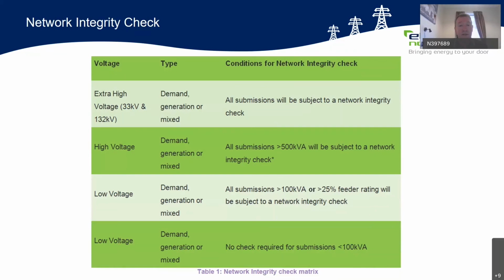So basically anything EHV would always be subject to a network integrity check. Any HV submissions over 500 kVA will be subject to a network integrity check. Low voltages, all submissions over 100 kVA will always be subject to a network integrity check, and LV schemes under 100 kVA do not require a network integrity check.